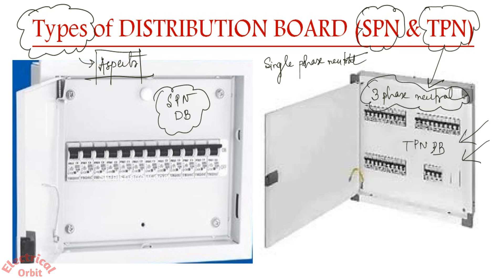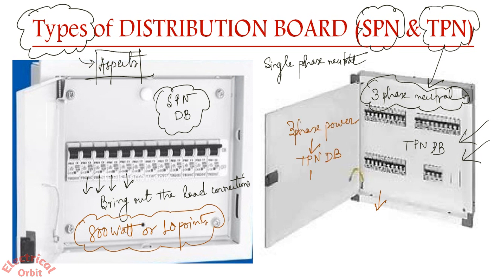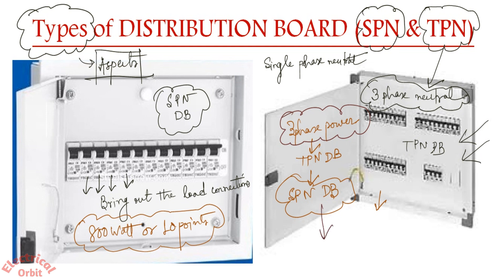From an SPN DB we bring out the load connections. There is a rule that from each individual circuit one can take a maximum of 800 watts or 10 points. For TPN, the three-phase power comes to the TPN DB and from here it is given to the SPN DB. So the TPN DB is the intermediate DB between the three-phase supply input and the single-phase output.